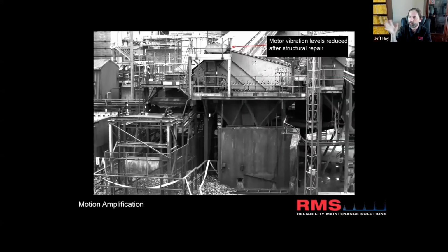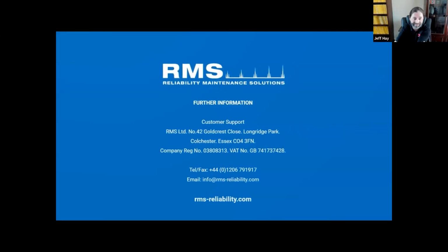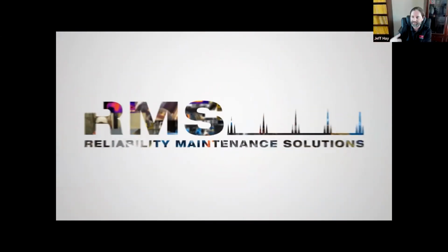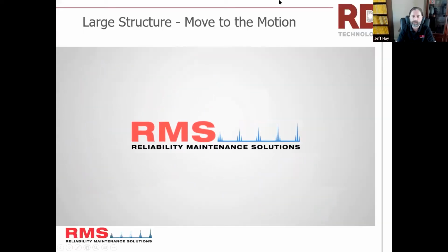Lots of times I think it's kind of a paradigm shift in the way you think. We're taught, well, you see a peak, and it's a 1 times, but with the camera you can actually literally see what it is. You just see the foot lifting up off the ground, and you can confirm it. You can see the looseness, and what's contributing to that motion. So that's where you can figure out what the cause is.